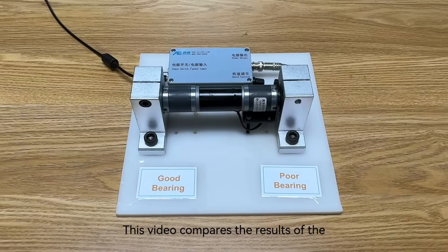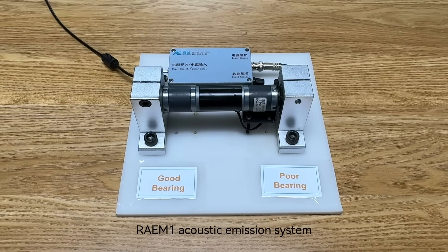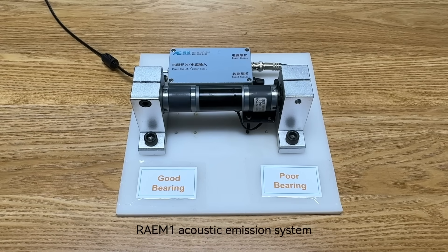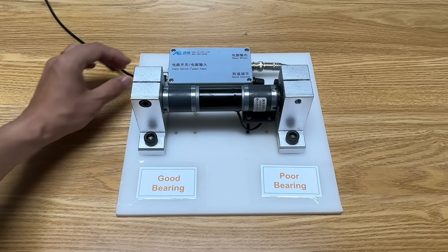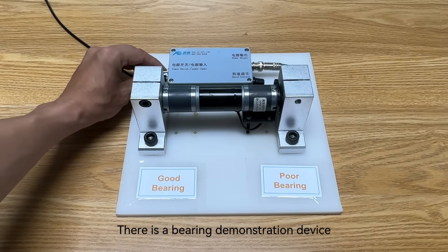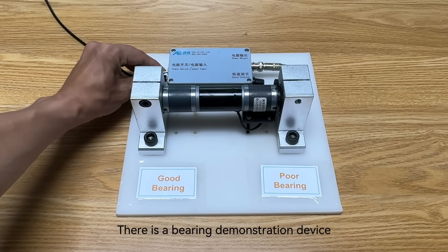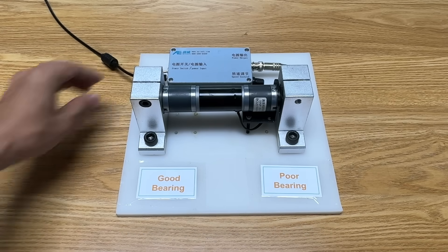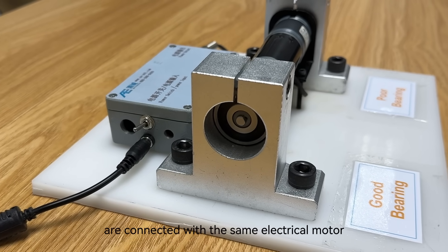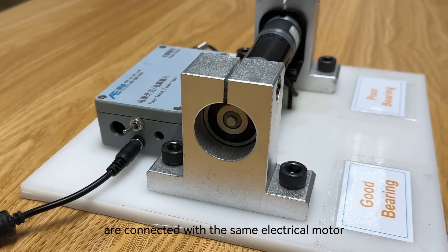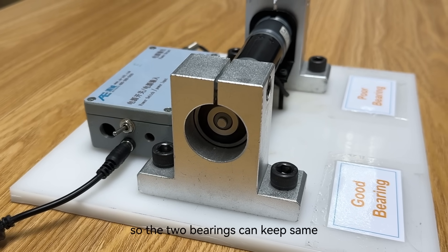This video compares the results of the RAEM-1 acoustic emission system detecting good bearing versus poor bearing. There is a bearing demonstration device where a good bearing and a poor bearing are connected with the same electrical motor.